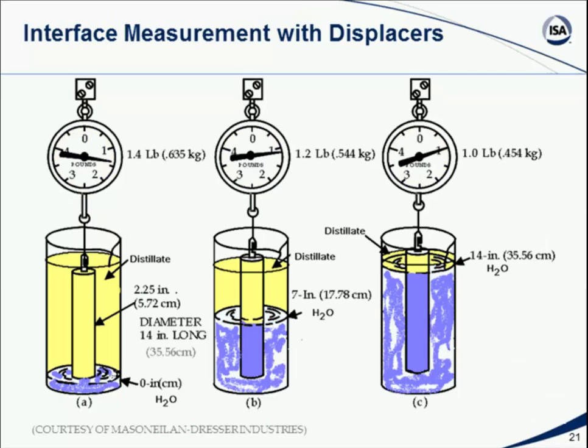What if what I'm trying to measure is not so much what's in the tank, but what's in the bottom of the tank? So let's go back to the example of a large storage tank at a refinery, and the tank is holding gasoline or kerosene. Over time, water seeps in and starts filling up the tank, or comes in as water that's actually in the refined products due to the refining. And so eventually, water collects in my tank and slowly builds up. And I want to know not the level of the overall liquids in the tank, but how much of that is water. So my tank is, in this case, a 14-inch deep tank. But how much of that is refined product and how much of it is water?